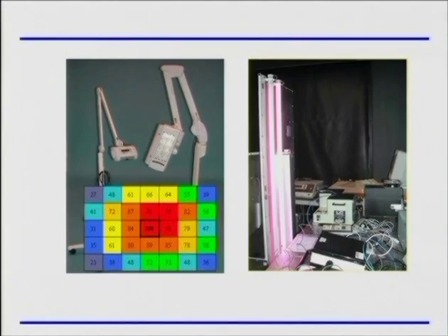Now, this is just showing you a grid. This is 1 centimeter squares, and we're looking at the light output from the 128 device. We calibrated our meter, and then we did measurements over a little simple grid to see how uniform the light distribution is. So you've got a patient, you want to expose some sort of superficial cancer, BCC or whatever, to light from this device. How uniform is your light? Nobody's going to tell you. You're going to have to measure it.